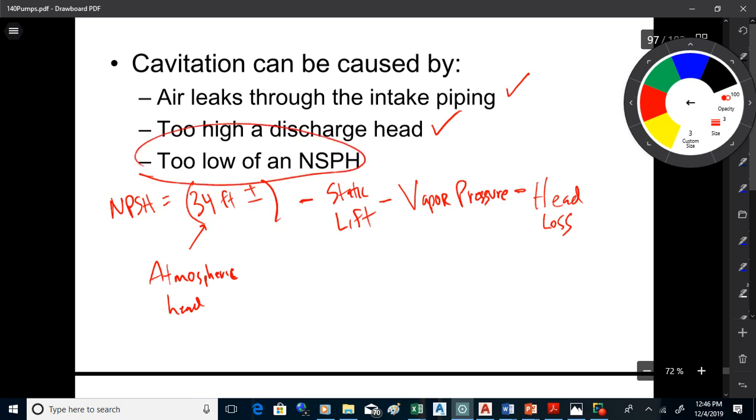What you can do is move the pump down if you can. Again, may or may not be able to do that. Also, look at that intake piping and try to reduce the constrictions, fittings, that kind of stuff in it. Make a nice, clean, open path to get the water up to the pump. That'll reduce cavitation. Yeah, somewhere they have a slight reducer before the actual pump itself. Yeah, and that's trying to get that head loss down.